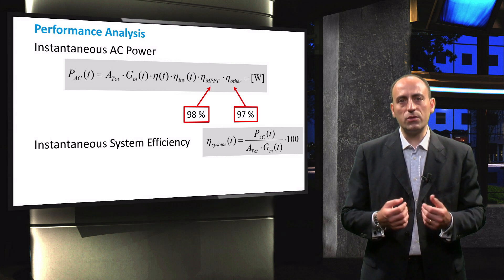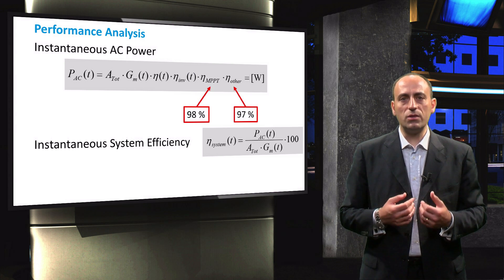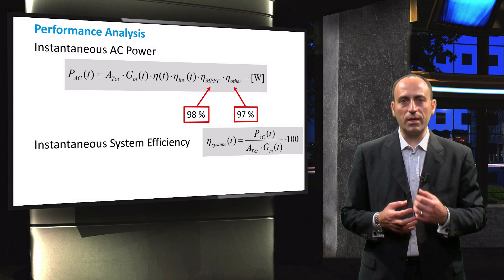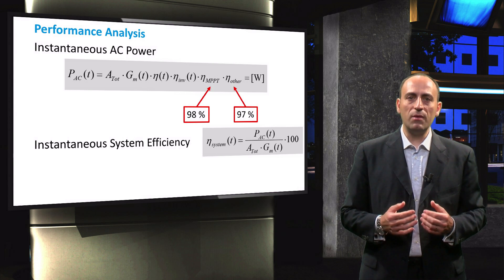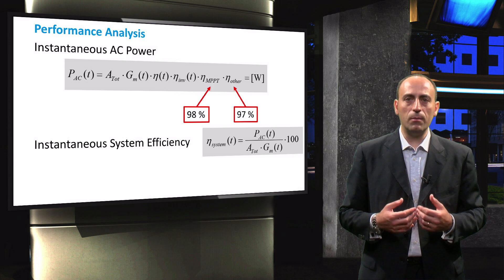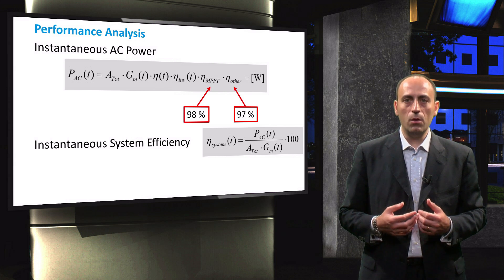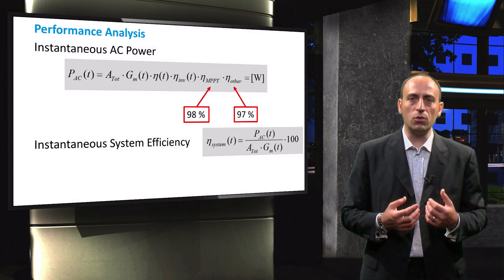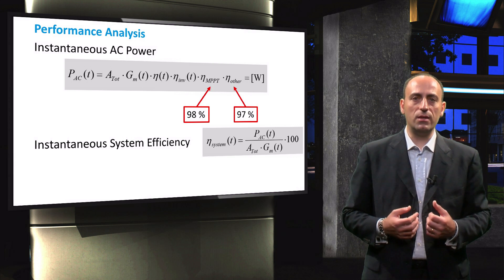Following the instantaneous AC power, the instantaneous system efficiency, eta system, can be calculated. The system efficiency is equal to the AC power output divided by the power incident on the modules, which is equal to the product of the total module area and incidence irradiance.